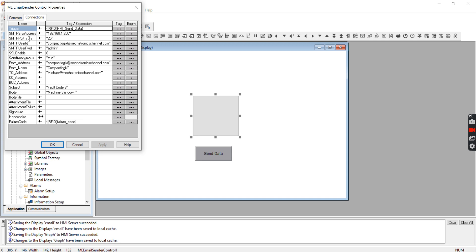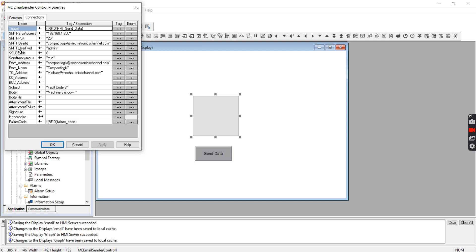Then you're going to put in the SMTP server address, which in the first video if you watch that, we set it up as 192.168.1.200. Now remember that this has to go in quotation marks - it is a string. And if you wanted to you can set tags to all this so you can customize all of these to be whatever you want. Then you're going to put in the port number, the SMTP port number for your email server, which is 25. That is the standard port number for SMTP.